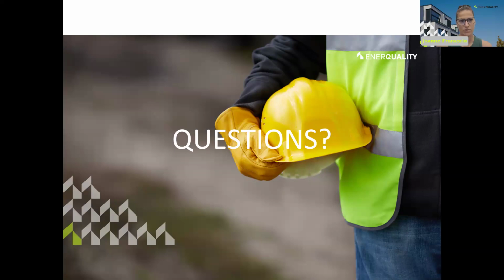Okay, thank you. So hopefully that helps, Sanford. Next question from Cindy. Is there a maximum recommended distance from the hot water tank to the drain water heat recovery? We find that, as in the examples I gave earlier, you had an increase of 12, 15 degrees Celsius in the temperature. So roughly, if you have cold water, let's say call it 10 degrees, you end up at 22, 23, 24 degrees Celsius preheat temperature, which is pretty much room temperature. So we find that, especially with PEX piping, there's really not any heat loss to the environment. So usually the length is not a big issue in terms of heat loss.